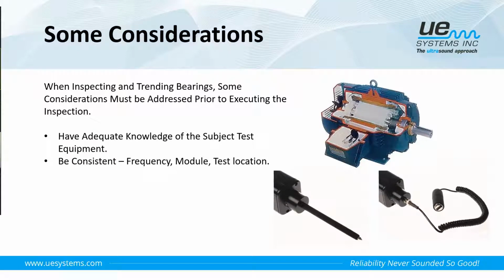We have to be consistent. We need to have the correct frequency with which we're monitoring our assets with our technology. We need to make sure that the modules that we're using are the same each time. And we need to ensure that our test location, our test point where we collect our data from, is the same as well. We need to establish an operative baseline so we can start looking at, trending and comparing our data over time.